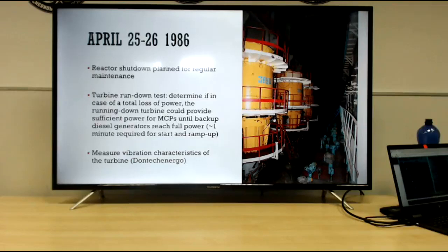So do you know how many of these pumps were in the power plant? There were 4 pumps on the southern side and another set of 4 pumps on the northern side, so 8 total — for one block. Each block had 8 pumps, and during normal operation, 3 on each side were operating while one was on standby. Amazing piece of machinery — huge, really complicated machines.